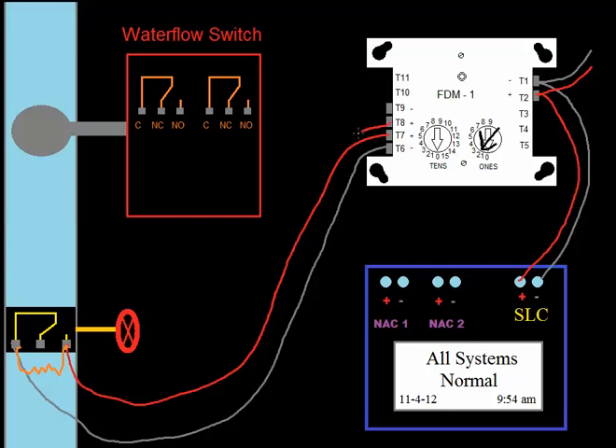Now I'll hook up the water flow the same way, positive to either one of these. The water flow switch is typical, the tampers usually have two terminals as well, but just for simplicity I only drew one. So we're going to go common normally open with the resistor in parallel.